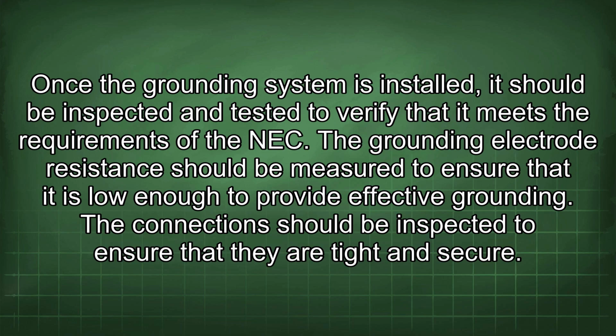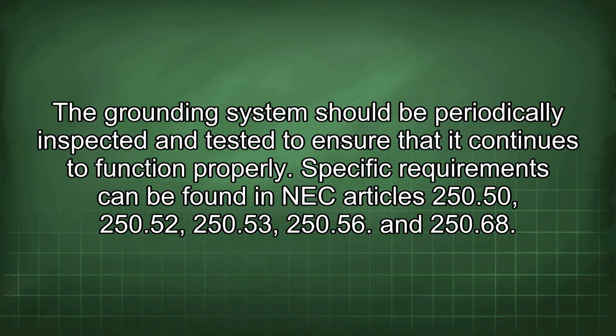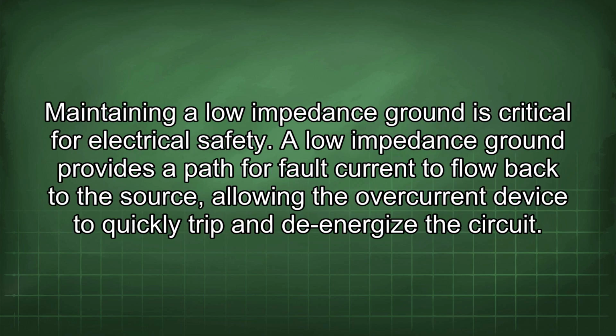The connections should be inspected to ensure that they are tight and secure. The grounding system should be periodically inspected and tested to ensure that it continues to function properly. Specific requirements can be found in NEC Articles 250.50, 250.52, 250.53, 250.56, and 250.68. Maintaining a low impedance ground is critical for electrical safety.